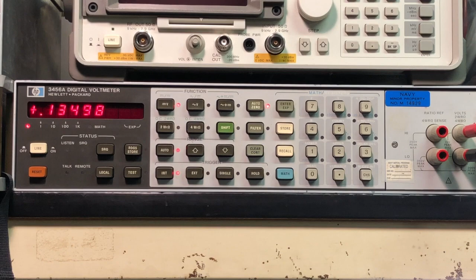Now, the reason it needs to run for 24 hours is because this oscillator, the ovenized crystal oscillator, is on all the time, and it needs to stabilize and come up to temperature before you make any adjustments. If you make an adjustment on it and it's not up to a stable temperature, then you might come back a day or two later and find that your adjustment has drifted a little bit. So once it comes up to its normal temperature internally, it's very, very stable and won't drift at all, but you have to give it time to do so. So again, they do mention 24 hours in the service manual, so we'll go ahead and follow that and just let it sit here on the bench, and then I'll get things connected, and we'll continue from that point.